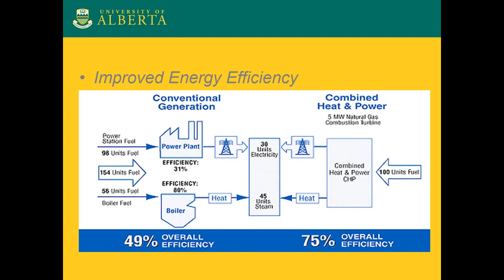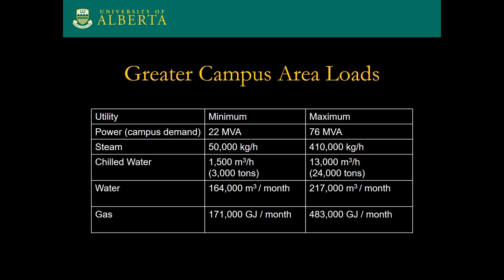Why district energy? Really, bottom line, it's just a lot more efficient. If you take a typical system, and I think we all know this, a remote power plant, which has got all those transmission losses, and you take your typical boiler in a building, which has got a certain efficiency, you add those together, compare it to a combined heat and power system, which is district energy, and you see the ratio there, 49% compared to 75%.